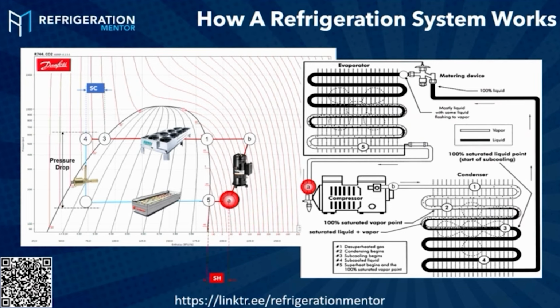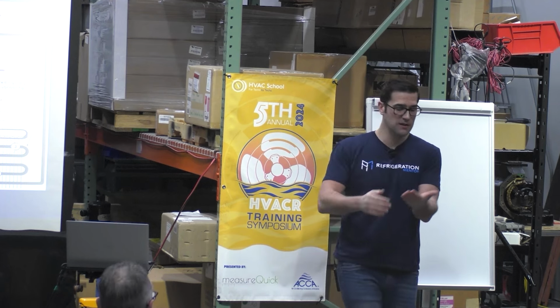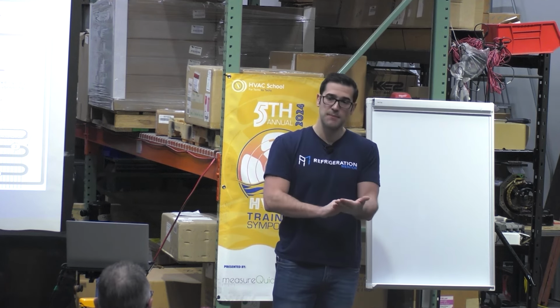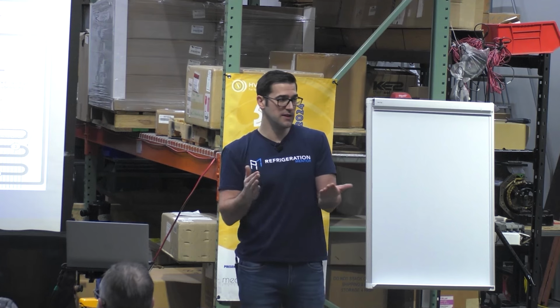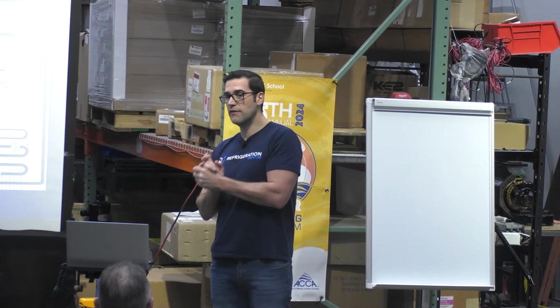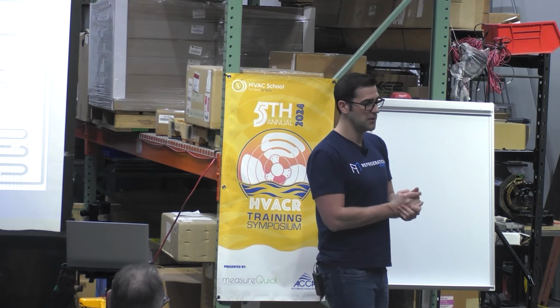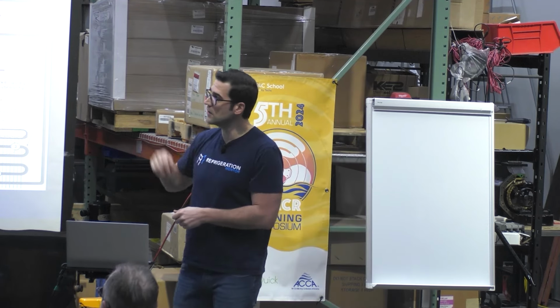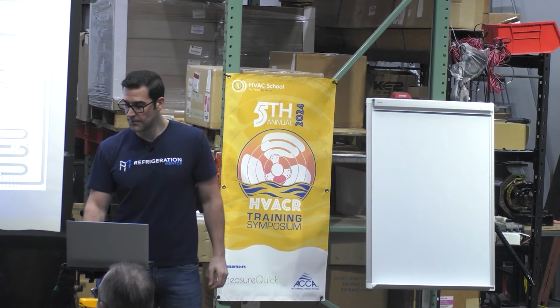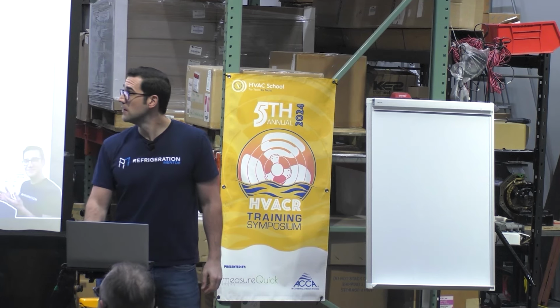This is subcritical. And does everybody know what I mean by it's subcritical, or anybody? Can they explain that? Somebody in here must know. Pardon? It still follows the PT chart, pressure temperature. So you go into your PT chart, whatever refrigerant in, and you can look at this temperature equals this pressure. Make sense? On every refrigerant, it has something called a critical point, which we're going to talk about. And I forgot to put like just a standard refrigerant up there, not a natural one. So the 744.